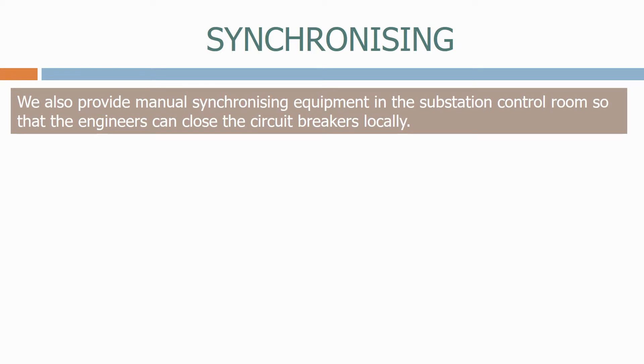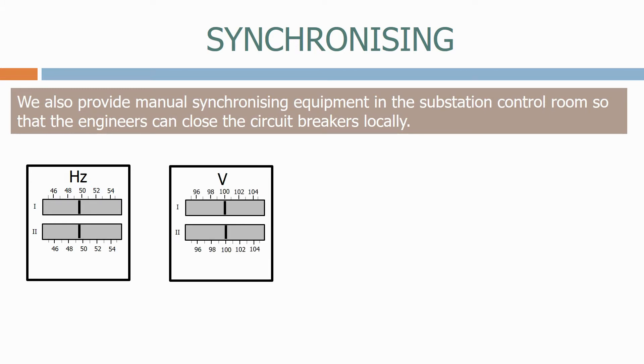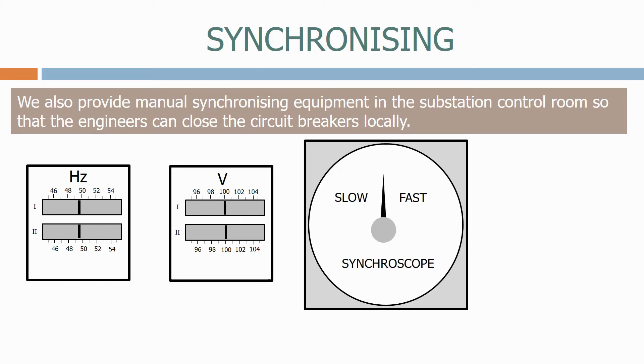We also provide manual synchronizing equipment in the substation control room so that the engineers can close the circuit breakers locally. To allow them to do this, we provide a frequency meter that shows the frequency on both networks, a voltmeter that shows the voltage on both networks, and a synchroscope that shows the phase angle difference between the two networks.